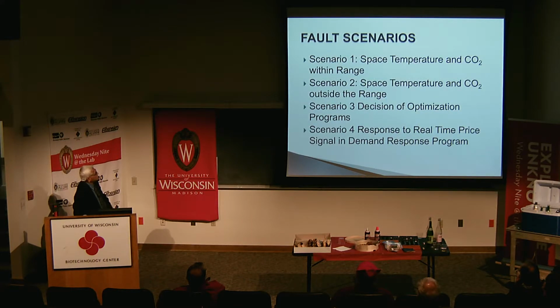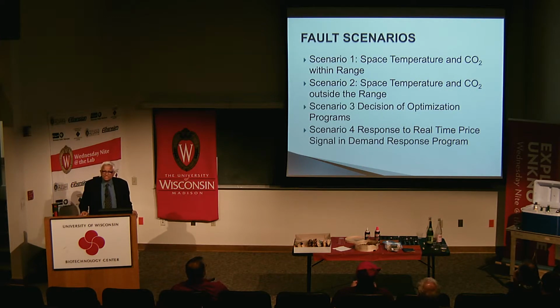Now, here is interesting things. What are the fault scenarios that I considered? One is, say space temperature and CO2 are within the range. For example, for CO2, they may say it has to be within 1,000 parts per million or 1,200 parts per million. And for the temperature, they may say it should be between 73 and 78. It is really left to the operator how he chooses the band.